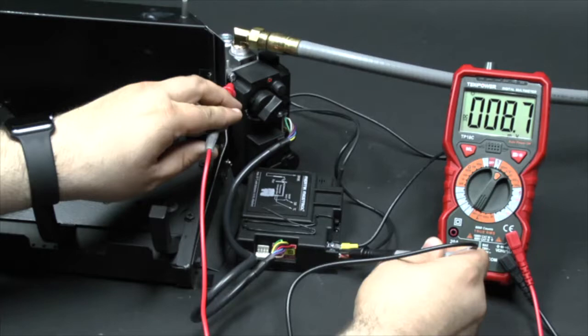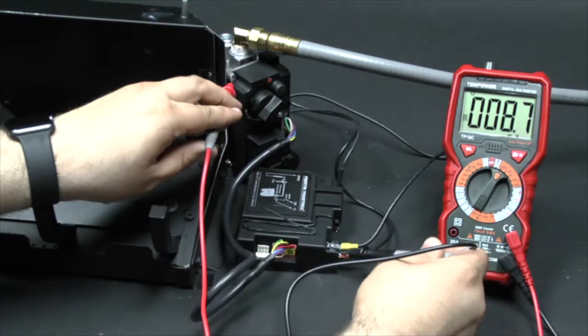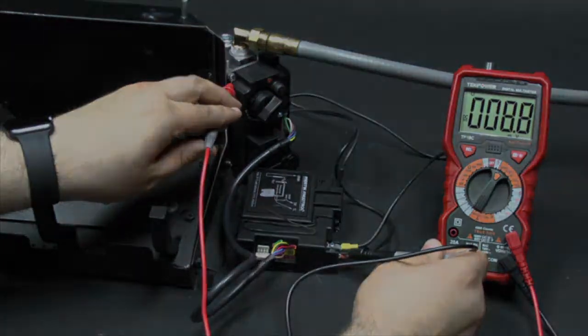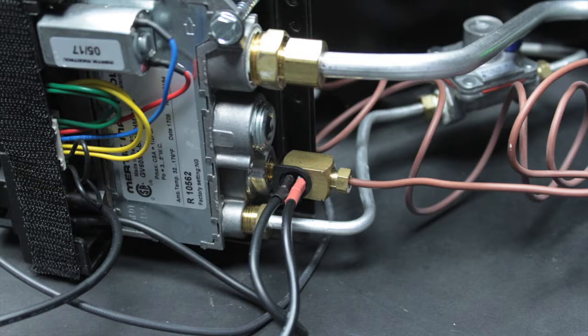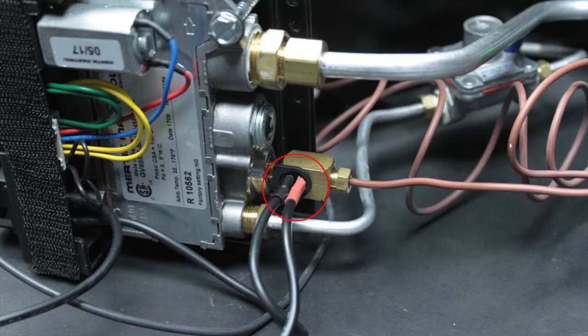Your voltage should be greater than 8 millivolts. If the voltage is still less than 8 millivolts, check the interrupter block and verify the wires are inserted properly and the junction is tight.